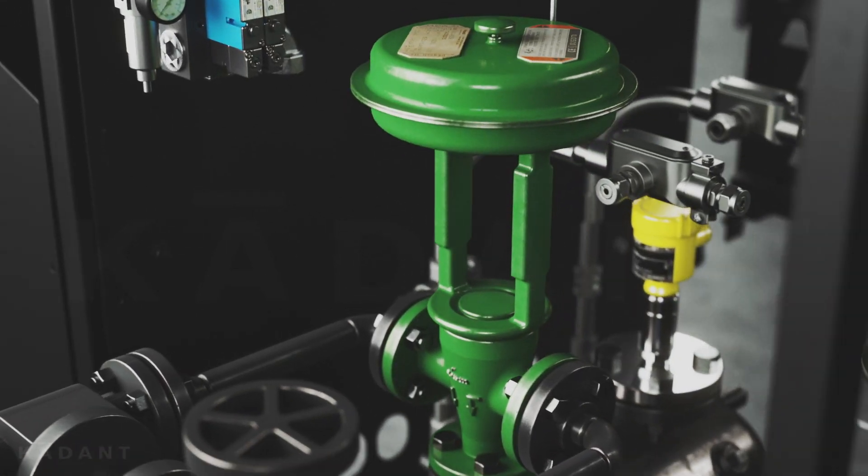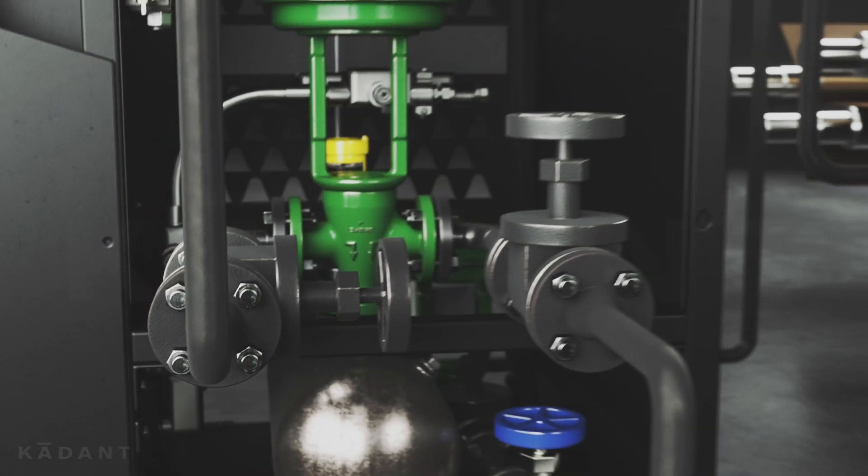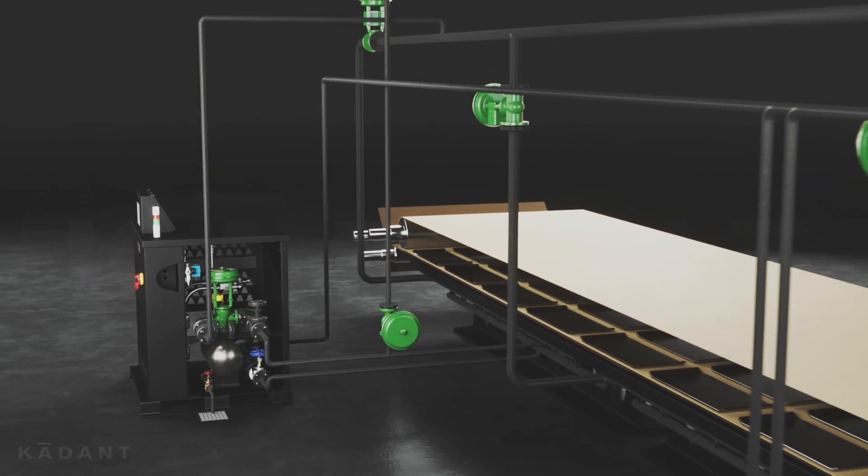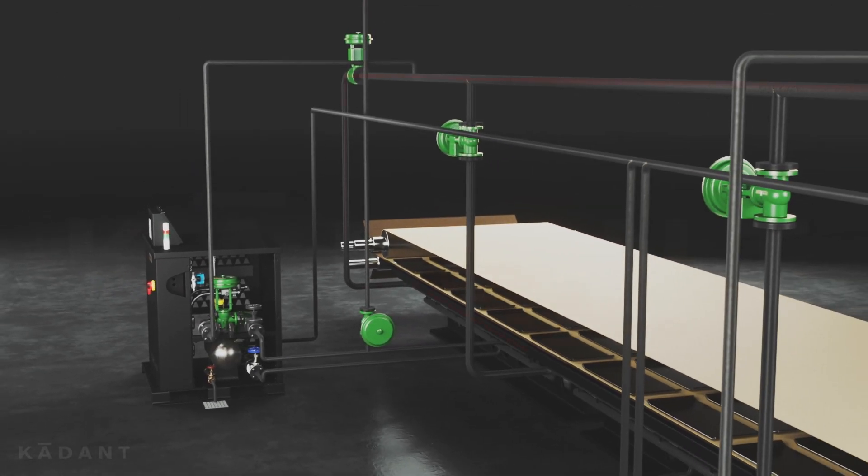Unlike diverter stations which require a minimum hot plate steam pressure to clear condensate, the ThermoZone station can clear condensate at steam pressures near zero.